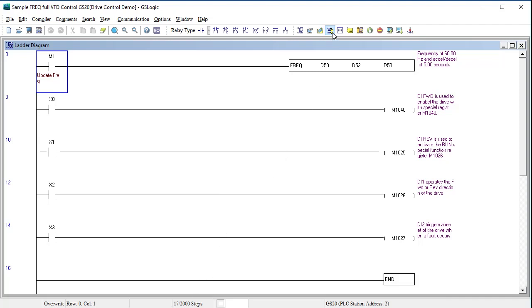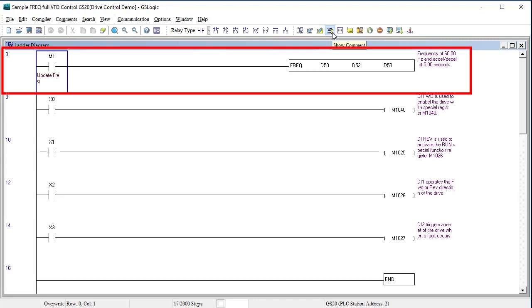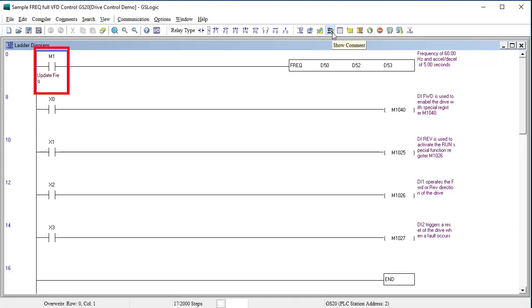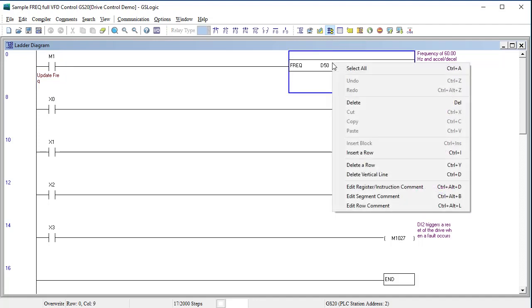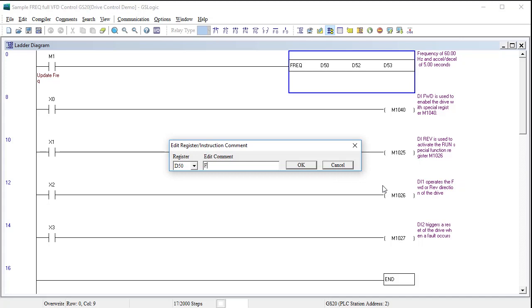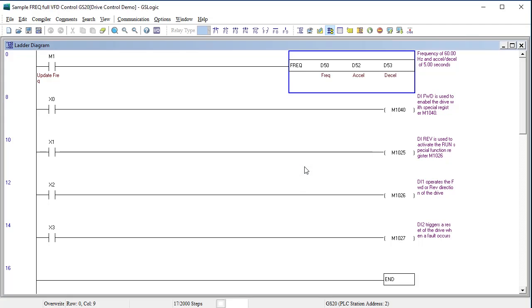If you don't see the comments then make sure the show comments button is on. Rung 0 says, when we set the general purpose M1 bit, set the frequency and ramp times. Now I can never remember which registers which, so let's right click and edit the register comments. D50 is the frequency with 2 implied decimal places, D52 is the acceleration with 2 implied decimal places and D53 is the deceleration with 2 implied decimal places. That's much better.